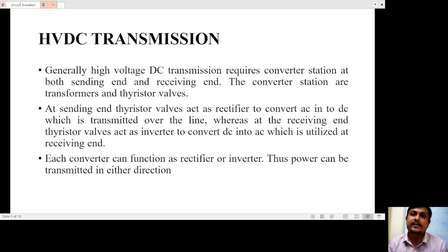In converter stations, basically, when we have to convert AC into DC, we use a rectifier, and when we have to convert DC into AC, we use an inverter. So at the generating station, the converter station works as a rectifier, and at the receiving station, it works as an inverter. Each converter can function as a rectifier or inverter.